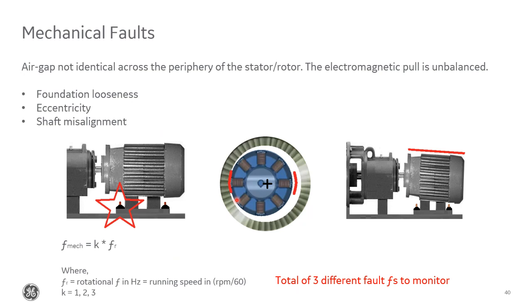The third type of fault category we can detect is the general category of mechanical faults. This accounts for anything that would cause the air gap to be not totally equal across the periphery of the motor. So basically, the electromagnetic pull is unbalanced. This might be caused by a loose foundation, or it could be that the rotor is rotating off center or rotating kind of wobbly back and forth. This is called eccentricity. Or it could be an actual shaft misalignment. All of these would cause some sort of a vibration.